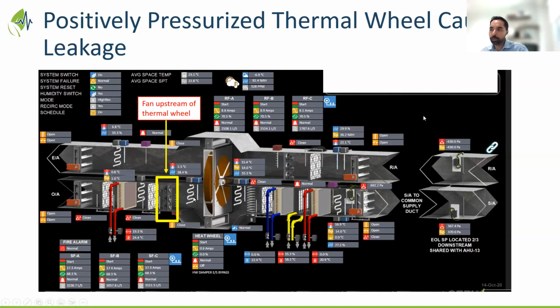But I see the point that it's kind of been done to avoid cross contamination, but a similar or opposite configuration, where the fans are downstream of the wheels, is being used in target hospitals with no particular issues about cross contamination.